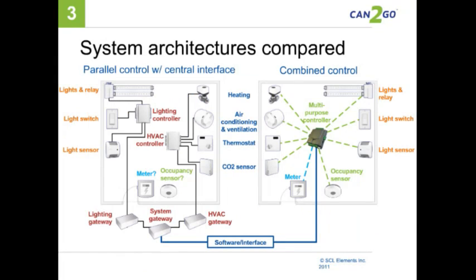This slide here tries to illustrate all this. On the left-hand side, you see the more traditional systems where you have parallel control for your HVAC and lighting. You see the lighting controller there, connected to a light sensor, your light switches, your lights, and actual relays. This is hooked up into a lighting gateway, which can then talk to your software building management system.